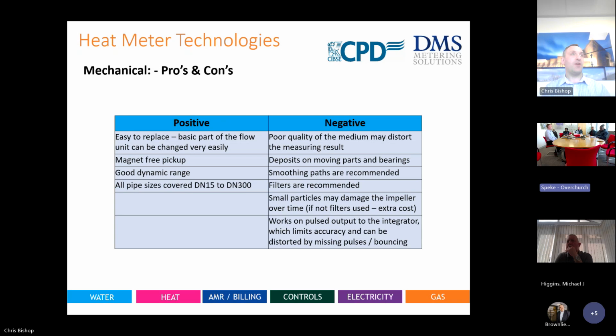So it's a 2-core cable that goes into a calculator. A lot of electrical contractors and even mechanical contractors understand the method, so to replace that is very simple. Dynamic range: because the mechanical meters have been around for so long, a lot of changes have happened in the water industry to accept more flow rate going through the mechanical meters. But that's kind of irrelevant in relation to a heat profile. For a water profile, it keeps costs down because you can put more water through a smaller location. And all pipe sizes are generally covered, from the domestic size to the larger DN300s.